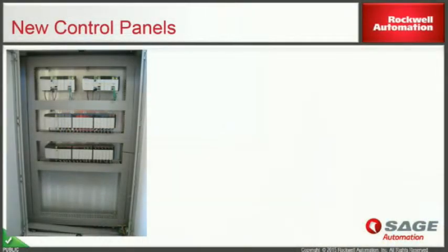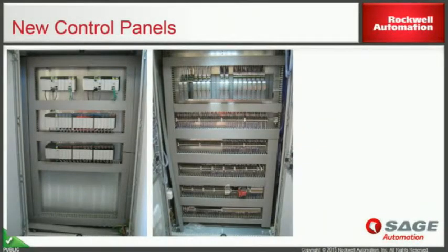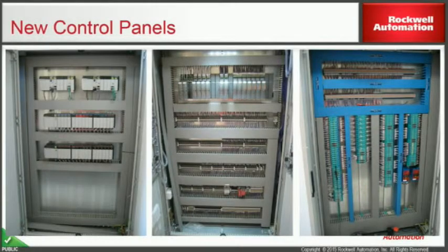Our control panels, this is an example of the control panel. So we've got our redundant CPU controllers up the top racks and a couple of I/O racks, all connected via separate DLR device level ring network from the peer-to-peer or SCADA networks. This is an example of one of the AADvance panels. These particular panels were built by Rockwell as part of their delivery to us, and we basically put those in the same suite of the panels that we supplied directly. And basically we ripped out all the existing panels. We didn't have the day or few hours turnaround requirement that Nearstar had, so we ripped out all the panels and put new ones in and re-terminated all the multi-cores. Sorry, and that's an example of one of our IS panels, new barriers and IS ducting there.